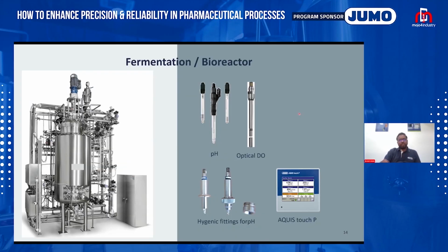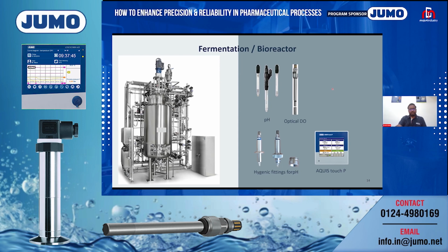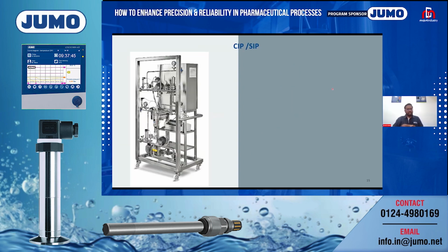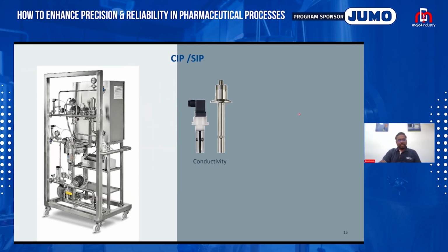JUMO has recently launched an optical sterilizable DO sensor for fermentation and bioreactors to measure traces of dissolved oxygen. The sensor is available in PPB as well as PPM range, and will be available after June 2024. It is recently launched, and its output is digital, RS-485. In CIP-SIP solutions, JUMO offers conductivity sensors for lower ranges as well as higher ranges.